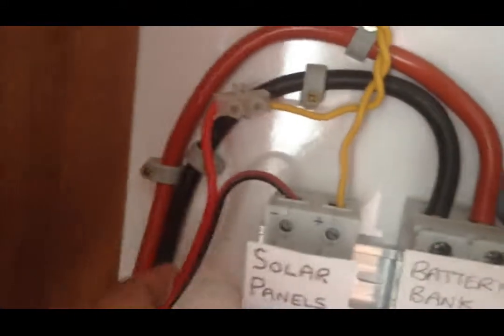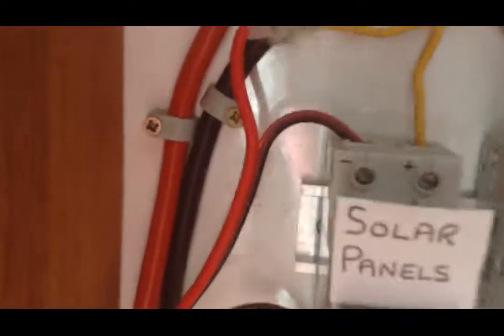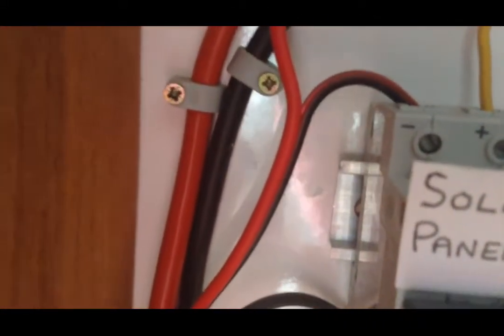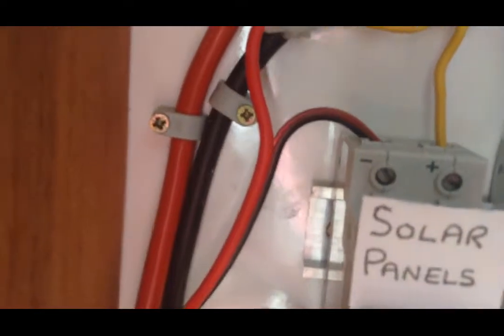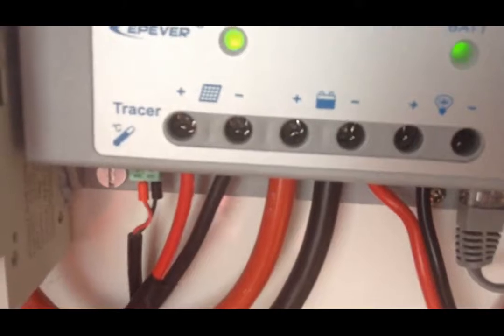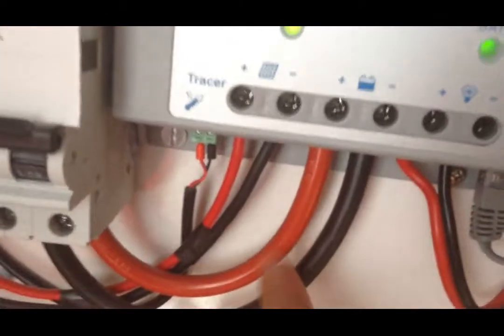I'll demonstrate this here. This is the wire from the solar panels. It's actually 20 amp wire, but it only needs to carry 6 amps. The wire going to the batteries has to carry 30 amps in this case, since the maximum output of the charge controller is 30 amps, so that wire is a lot thicker because it needs to carry a higher current.